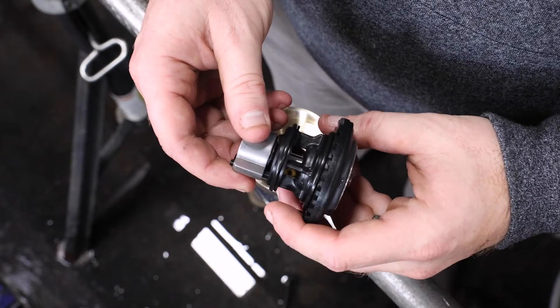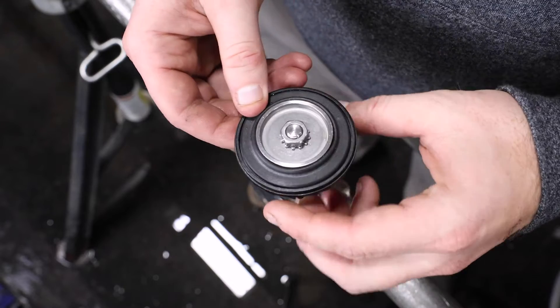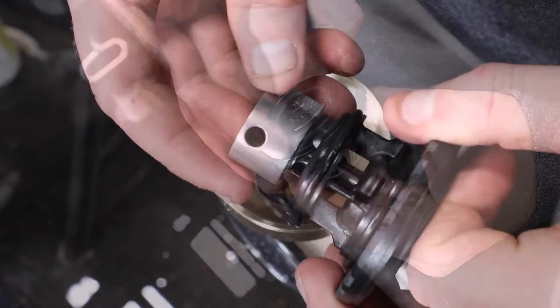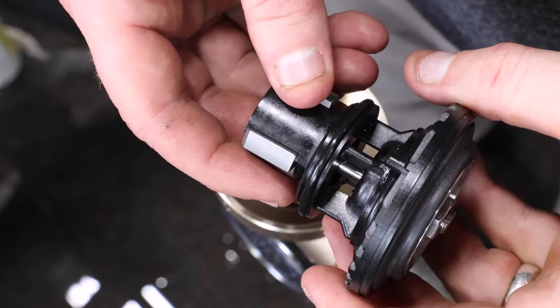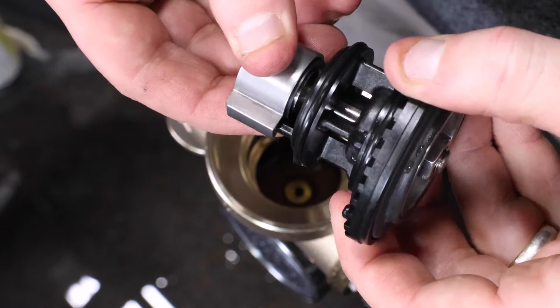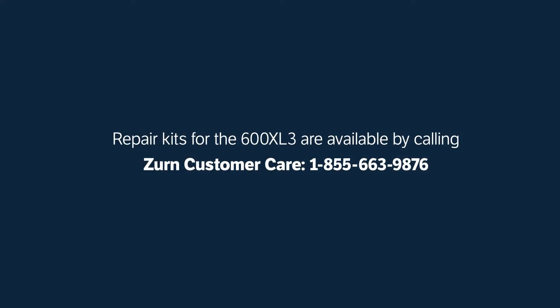Visually inspect both sides of the diaphragm for cuts, tears, or material degradation. Clean as needed. Inspect the seal ring and seat for any nicks, cuts, or other damage. If there is no visible damage to the body or internal parts, clean the parts as needed and reassemble according to the directions that follow. If there is visible damage to any of the parts, you will need to replace them. Repair kits for the 600XL3 are available by calling Zurn Customer Care at 1-855-663-9876.